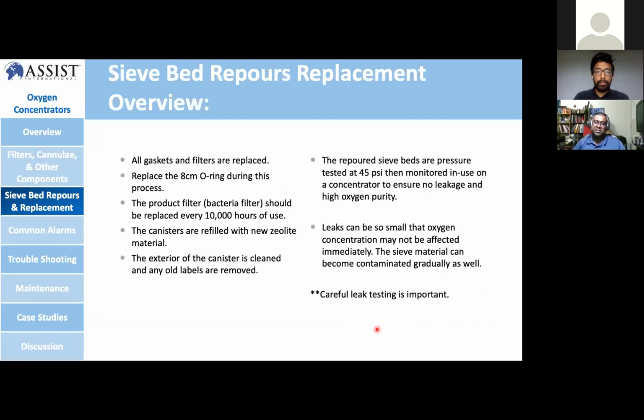So when you do sieve bed replacement, you always need to replace all the gaskets and filters. Replace the 8 cm O-ring during the process. I'll explain what the 8 cm O-ring is later. The product filter and bacteria filter should be replaced every 10,000 hours of use. And the canisters are refilled with new zeolite material. Make sure you clean the canister, remove the label, all that, and you can put the date of replacement.